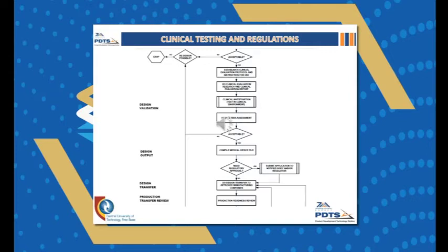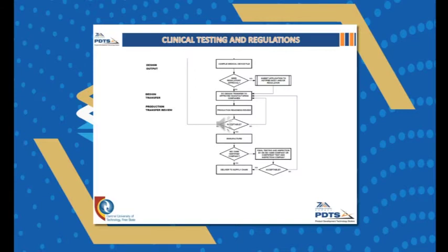Finally, with a safe and functional medical device, a review should be held to review the development documentation and the design output against the design input requirements, and the development input and output review should be completed. It is very possible for the production readiness review to be rejected, and the developer will have to perform a redesign and validation. The acceptance of the production readiness review will lead to manufacturing.